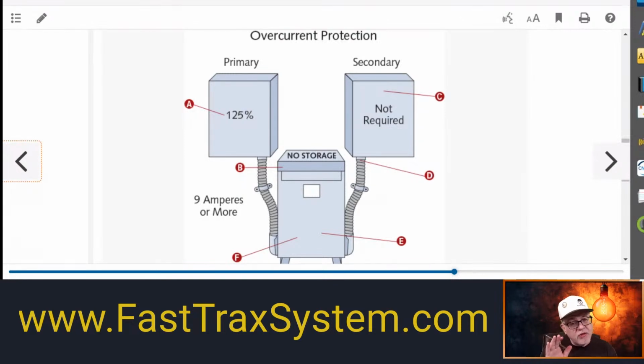Now, stick with me too if you're here and you're like, I know this stuff, because we're also going to talk about the conductor sizing, for example, if this happens to be a tap off of a feeder that's supplying a transformer, which is very common in a lot of commercial and industrial applications. So this is just easy because this is fed straight from a panel, coming straight to the primary, and then going down to the transformer. This one's straightforward. All right, so these conductor sizes. So now I have to have a conductor, even though we know that the primary side is 90.21, and what we did was we took it at 125%. That was the table. So typically, we're going to size the conductors equal to or greater than whatever the overcurrent protective device is for the primary, right?